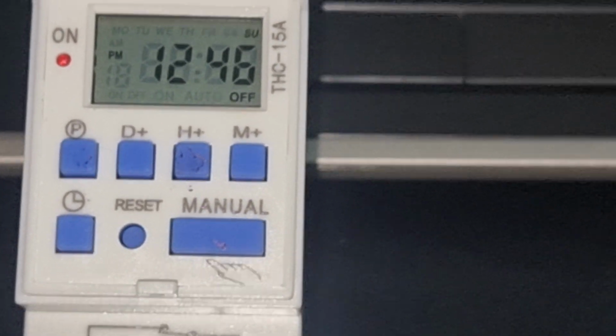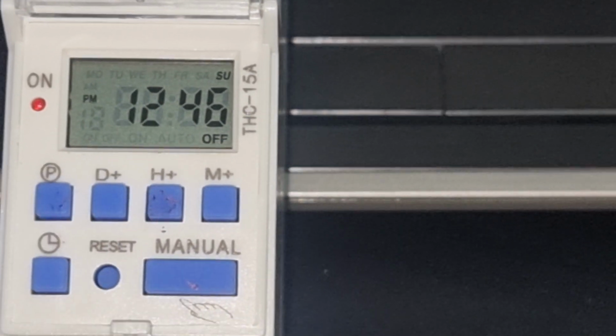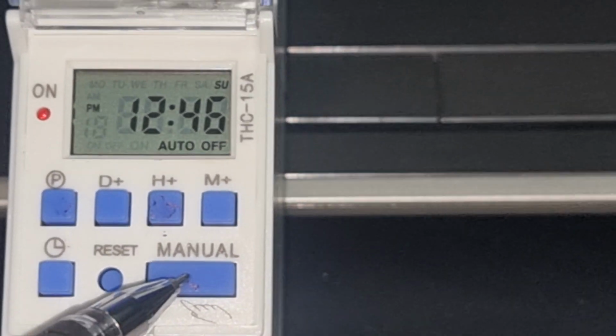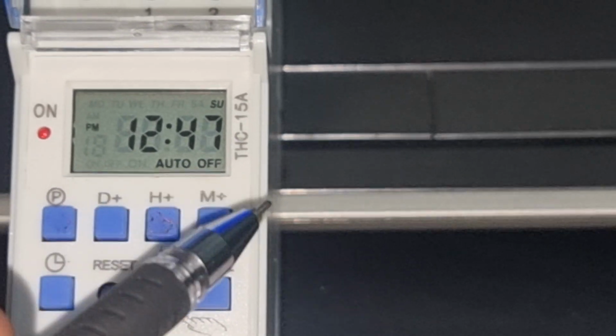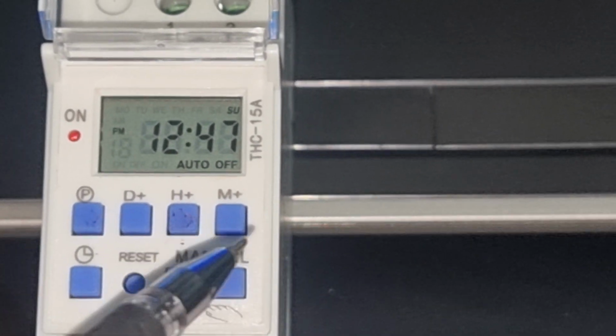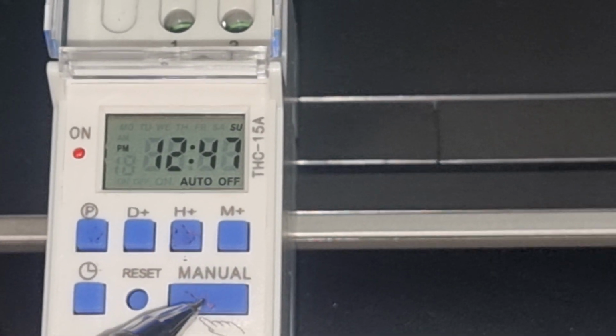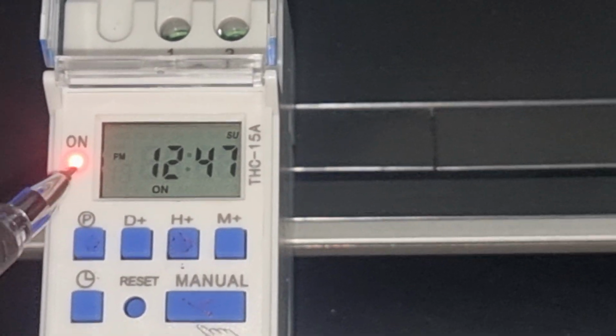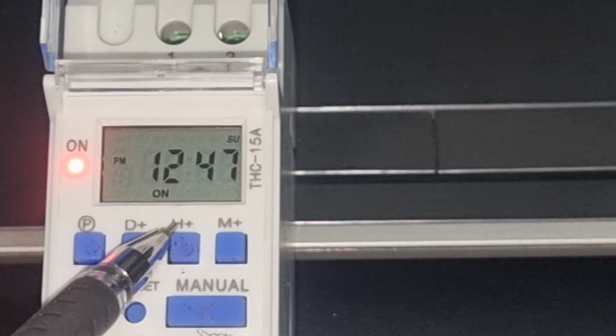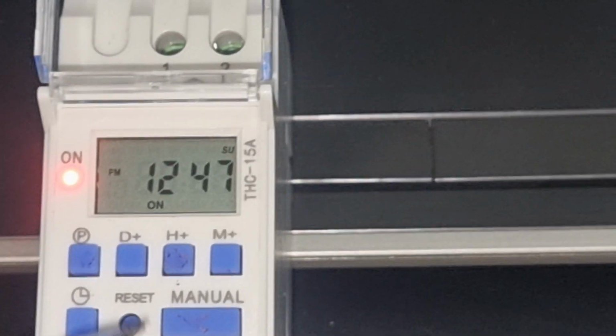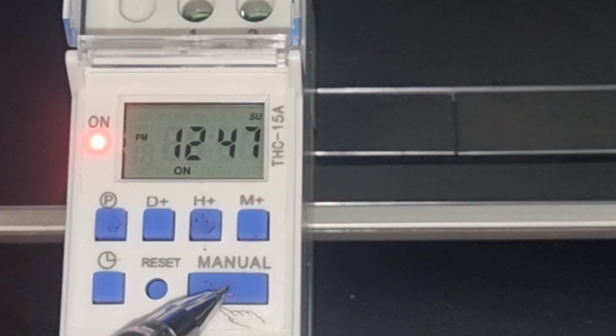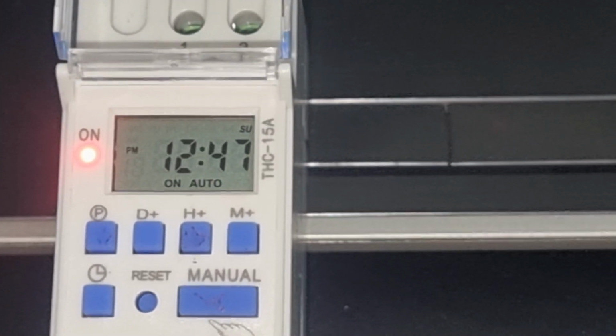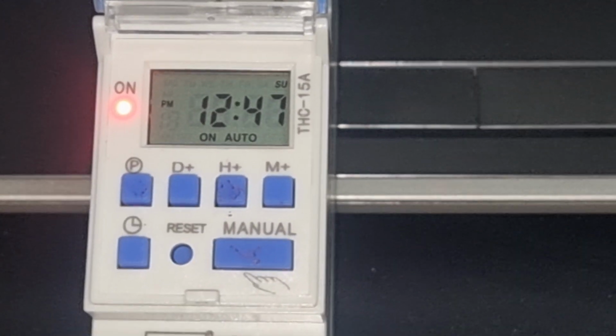When I have set all the times, before leaving the time setting, I must check the position. Now it is showing the position is off. I must put it to auto. See, there is auto. I put it on manually. Now it is auto off, meaning when the timer comes it will automatically go on. I press again manually, see, now it is on. On means it is only on, always on, nothing changes. So I must put it on auto here. I press auto, meaning now it is auto on or auto off as normal.